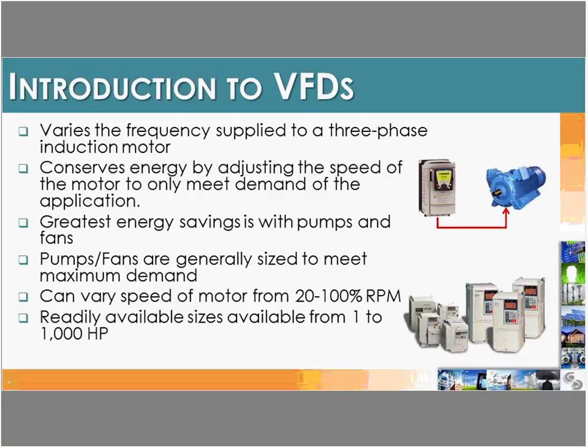A VFD does exactly what the name says — it varies the frequency supplied to three-phase motors. You might also hear the terms adjustable speed drive or variable speed drive; it's the same thing, just different terminology. They conserve energy by adjusting the speed of the motor, trying to meet the demand of a particular application — supplying the amount of power required, no more, no less. They offer the greatest energy savings opportunities with pumps and fans.